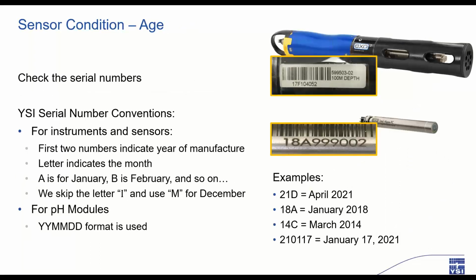Another important tidbit that I like to make note of is how old are my sensors? YSI makes this pretty easy and pretty simple to tell. Just at a glance, the serial number or lot number will give us a quick visual on age. Most YSI sensors and instruments have an alphanumeric at the beginning of their lot or serial number. The first 2 numbers would be the year of manufacture, while the following letter will indicate the month of that year, A being January, B being February, C, March, etc. We skip I because it's too close to the number 1.